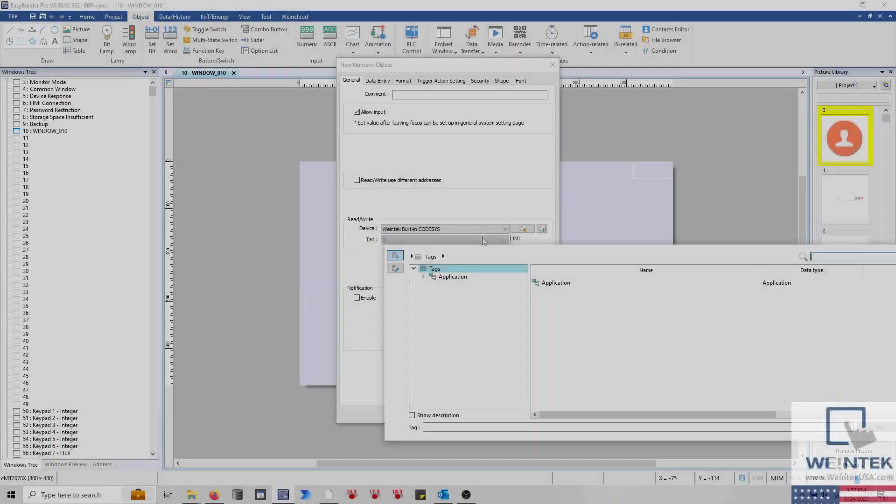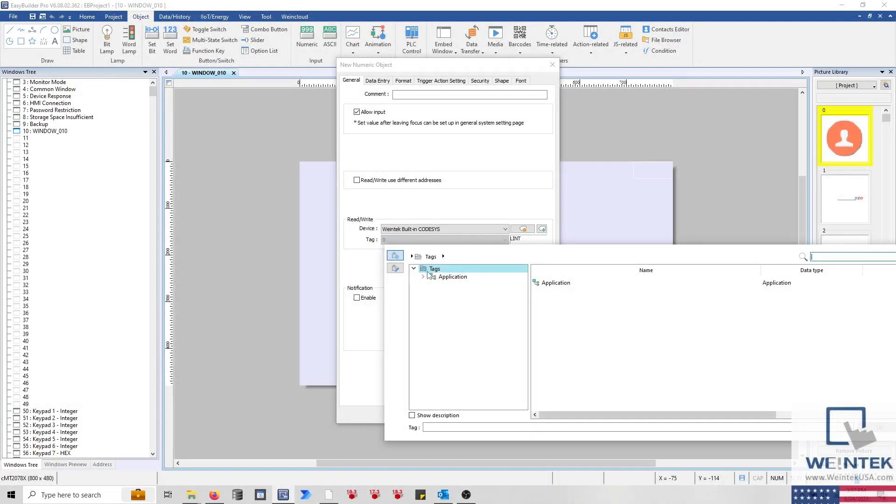If you add additional tags within your application at a later point, or if you change a tag name, please rebuild your project, ensure that those tags are selected within the symbol configuration object, and then click Generate Code within the Build menu to export these tags. Download this project to the controller and set the application in run mode. Import this tag file using the Import Tags option within the system parameters of EasyBuilder Pro, and you can then assign these tags to an object such as a numeric display or bit lamp.